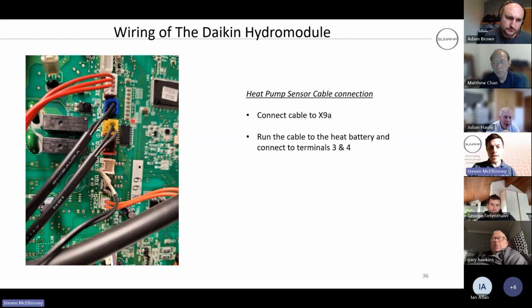You connect the cable to X9A, which is here. One thing I've noticed is, when an installer was having a fault, they were getting a tank sensor temperature error. I don't know if this came from the factory or was done on site by mistake, but this plug fits perfectly into that plug. So the installer plugged X9A into X22 by mistake, and obviously it was creating an issue. So swap them round, no problem.